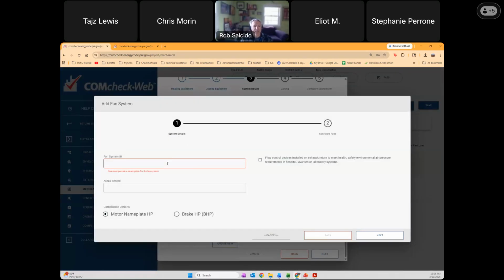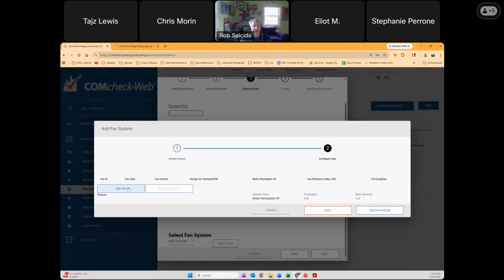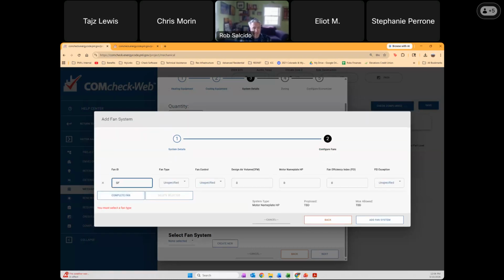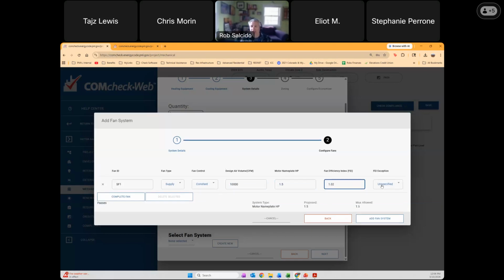For the fan system, I can just give it a name, fan sys 1, and decide, do I want to check on its motor nameplate horsepower or its brake horsepower? I'll start with motor nameplate, and here I can add a fan. I'll add in a supply fan. There are multiple types: you can do a supply, return, relief, exhaust. And then fan control, is it constant or VAV? And the volume, I'll just say it's 10,000. I'm really bad with CFM and horsepower, but I'll just give it 1.5. And then this should be fan energy index, and I'll give it a 1.02. There are also FEI exceptions. If they're met, you can select one of those and not have to enter the FEI.